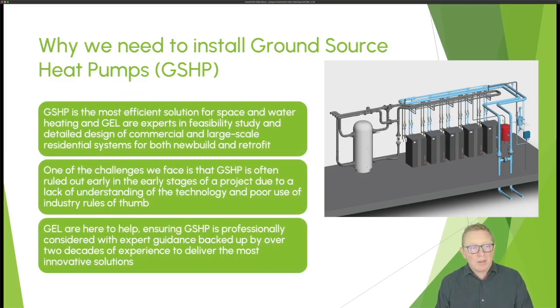So why do we need to install ground source heat pumps? Well, GSHP is one of the most efficient solutions out there for heating and cooling spaces, both for residential and commercial applications, and that applies to both new build and retrofit. But one of the challenges we face is that ground source is often ruled out before projects even get underway, right at the concept stage, because people don't really understand the technology - and engineers, even large consulting engineers, can be guilty of this, just relying on rules of thumb and ruling out the technology too soon.